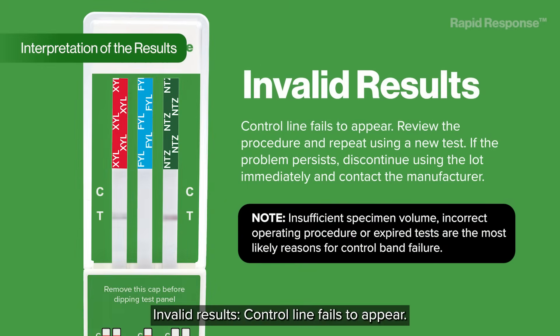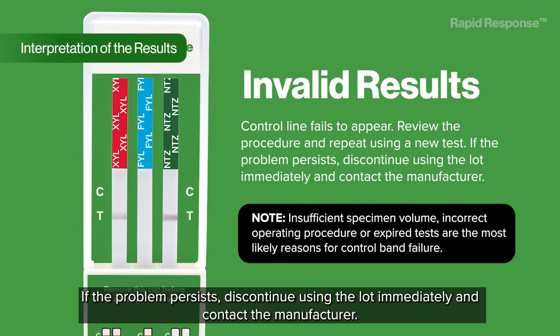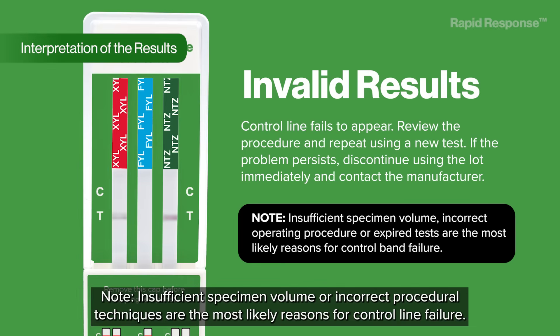Invalid results: the control line fails to appear. Review the procedure and repeat using a new test. If the problem persists, discontinue using the lot immediately and contact the manufacturer. Note: insufficient specimen volume or incorrect procedural techniques are the most likely reasons for control line failure.